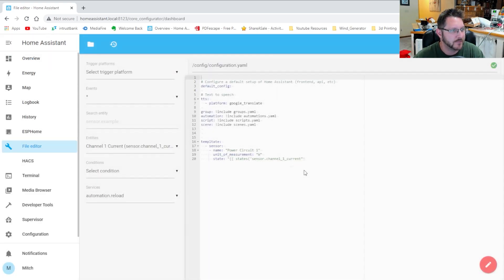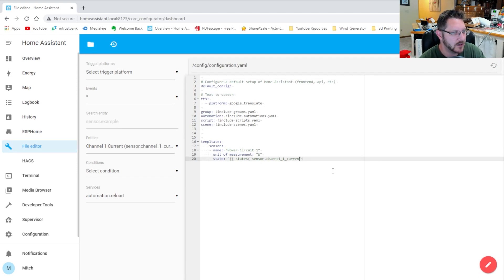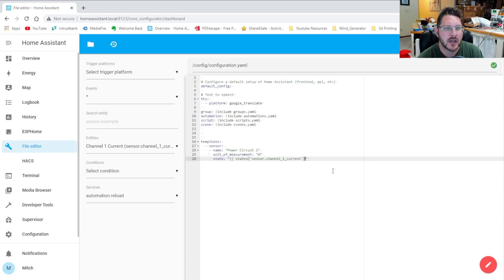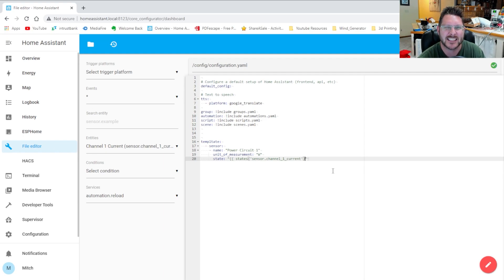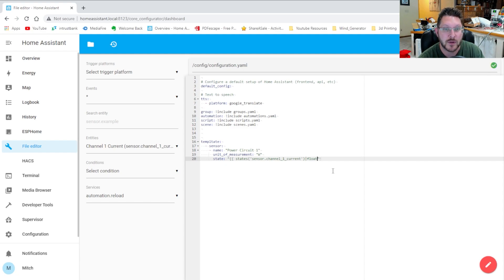You can always cut and paste that name and go back to your File Editor and put it in there. Then we close the parentheses. However, this is a states-type value, so we need to typecast it as a float — pipe it to float. Otherwise I think it treats it as an integer and truncates some of your numbers. So we pipe it to float, then multiply it by 20.